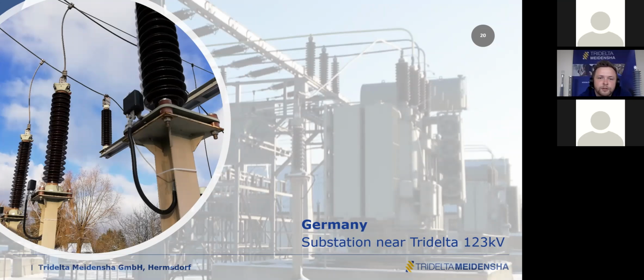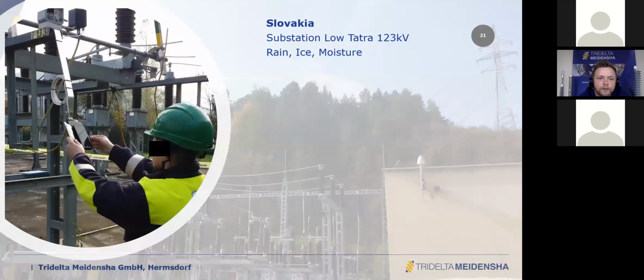So that was the very early beginning of the first devices which we have installed in a substation very close to our factory. Classical retrofit installation on existing surge arresters. Very easy, just bend down the cable and install the smartCOUNT data logger, and then carry down the cable from the transponder pad and install it on the bottom of the steel structure you see here. It took us 8 minutes for one set of smartCOUNTs. Very easy installation and very good results.